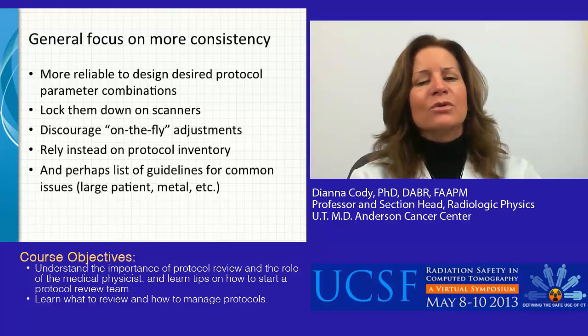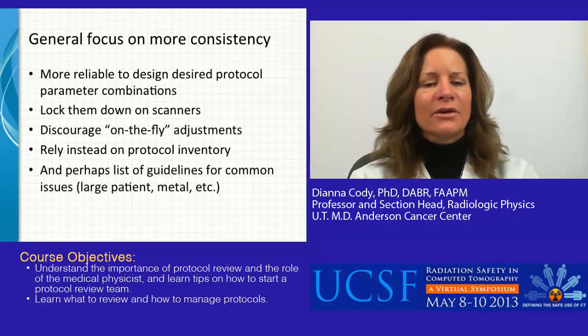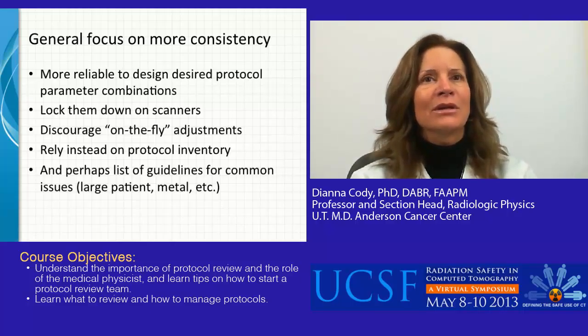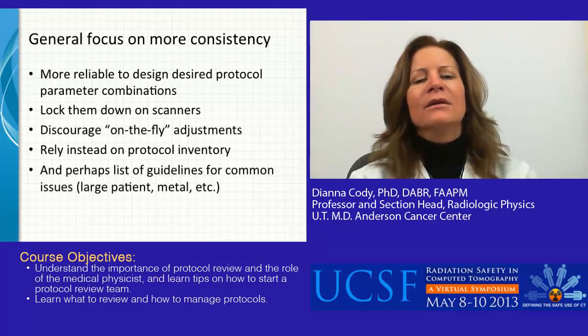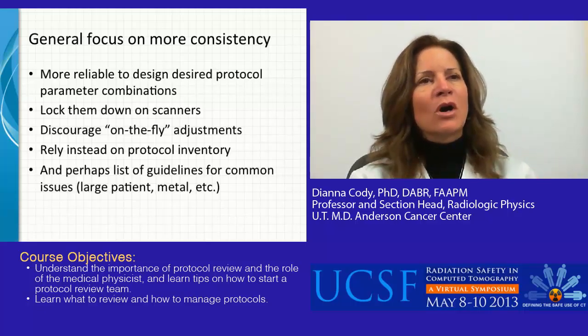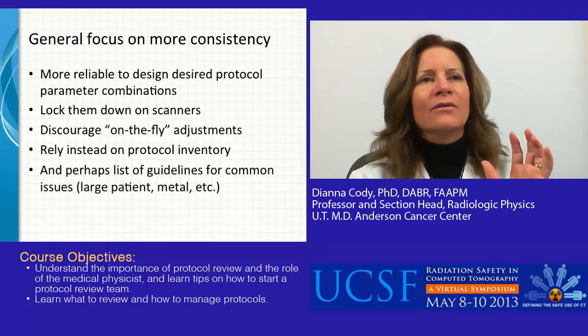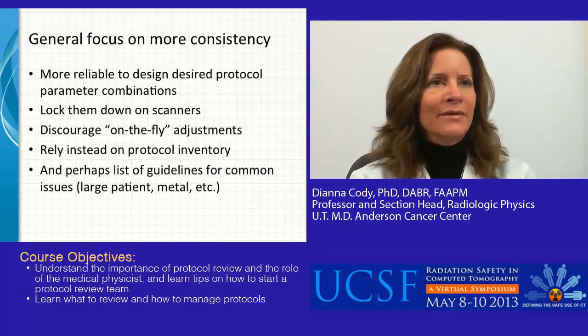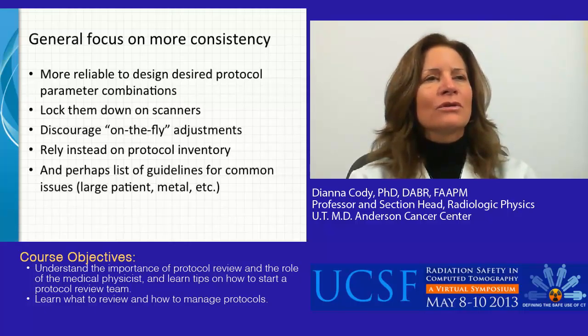We wanted to design our desired protocol combinations. It's not one parameter that drives any exam. It's the combination of parameters. So we wanted to really look at them all together and figure out the best combination, lock them down on the scanners, discourage on-the-fly adjustments, and instead rely on our protocol inventory.